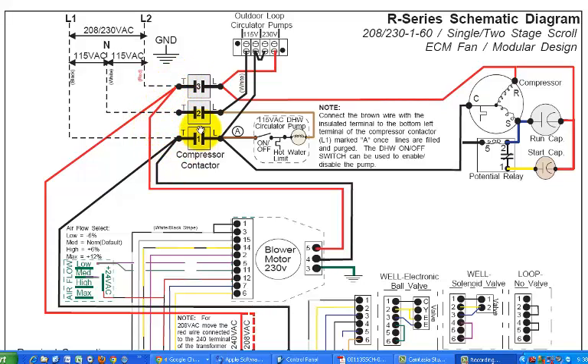And a critical thing to note there is that those are going to be constantly hot, or at least they're going to be hot whenever the breaker is turned on, so that we're feeding power in through L1, L2, and the neutral wire. So when that breaker is on, then we're always going to see a potential difference of the 230, 240 or so volts between that terminal and that terminal. So what they're doing is pulling that off, and in this line here, if we follow it, we're coming over and feeding the blower motor. Similarly, off the L1 terminal, we're also coming over and feeding the blower motor.